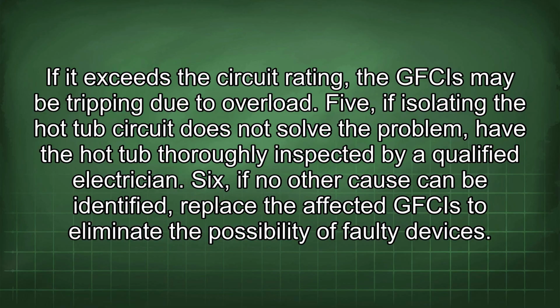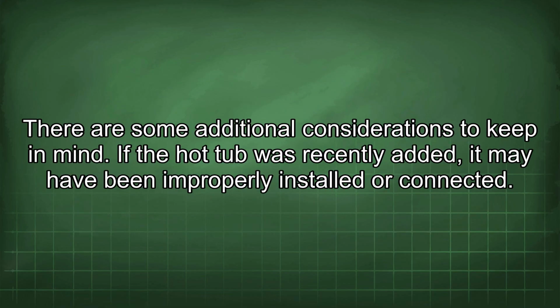5. If isolating the hot tub circuit does not solve the problem, have the hot tub thoroughly inspected by a qualified electrician. 6. If no other cause can be identified, replace the affected GFCIs to eliminate the possibility of faulty devices. There are some additional considerations to keep in mind.